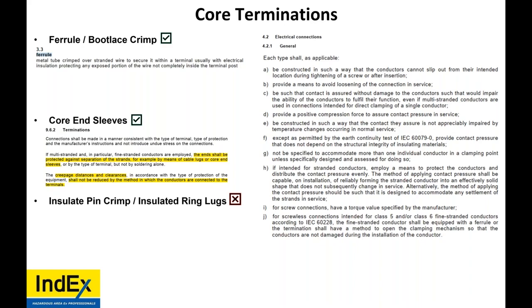Now, core end sleeves. It's just another word for crimp, core end sleeve. The creepage and clearance distance in accordance with protection technique shall not be reduced by the method with which the conductors are connected to the terminals. Insulated pin crimps seem to do that. Endless evidence throughout the industry.